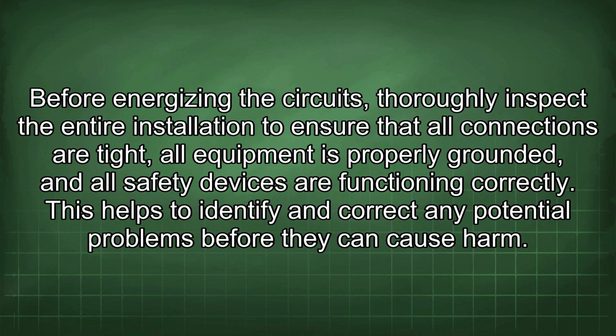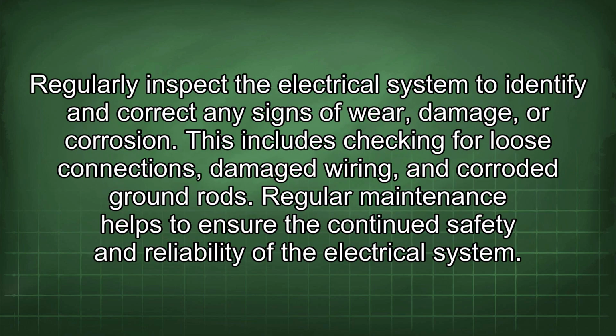Before energizing the circuits, thoroughly inspect the entire installation to ensure that all connections are tight, all equipment is properly grounded, and all safety devices are functioning correctly. This helps to identify and correct any potential problems before they can cause harm. Regularly inspect the electrical system to identify and correct any signs of wear, damage, or corrosion. This includes checking for loose connections, damaged wiring, and corroded ground rods. Regular maintenance helps to ensure the continued safety and reliability of the electrical system.